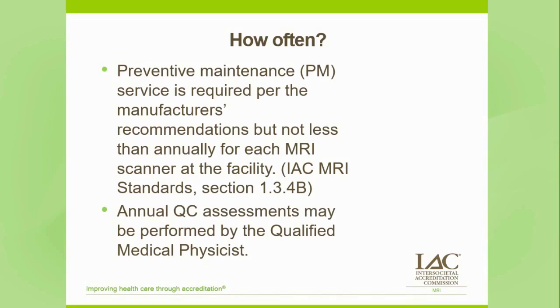A recent revision of the IAC MRI standards, effective November 15th, 2020, allows a medical physicist to perform an annual QC assessment. As a result, the IAC MRI accreditation application has also been updated to allow submission of the medical physicist's annual QC in addition to or in place of the engineer's PM. The takeaway is that a PM or an in-depth QC assessment must occur at a minimum of once per year, and may be performed by a service engineer or a medical physicist.